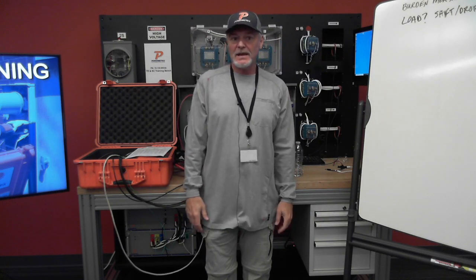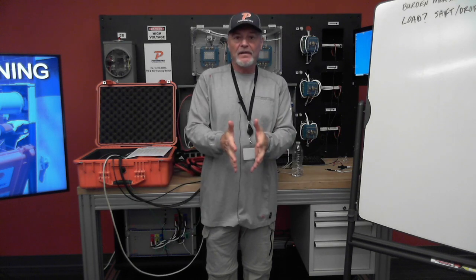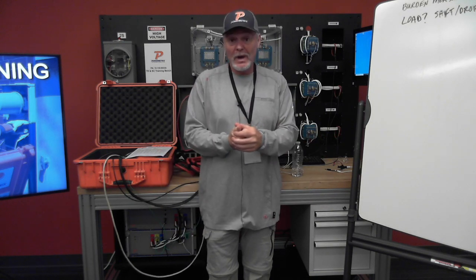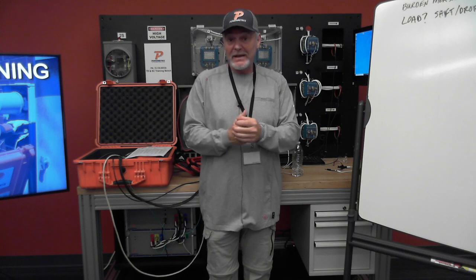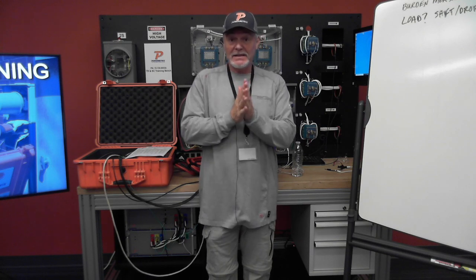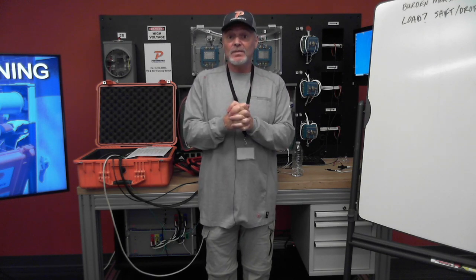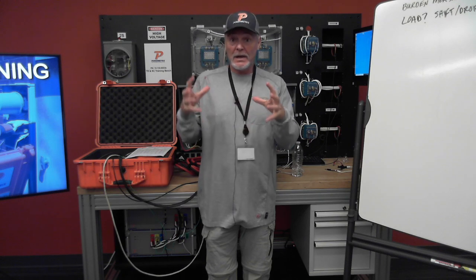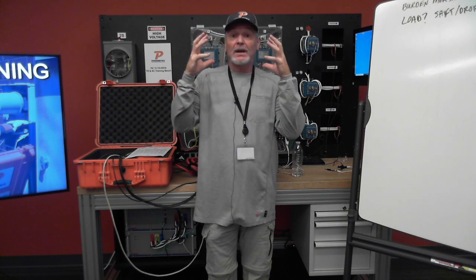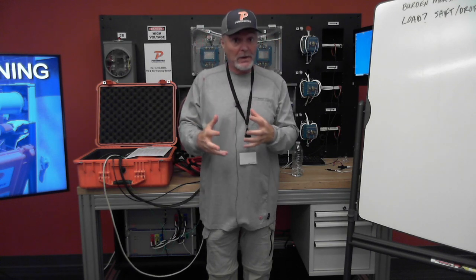In this case, it had got us down to the point where if it hadn't been corrosion, we definitely would have had to have pulled that CT and taken a look at it. So hope you got a lot out of this one. It included a lot of common sense troubleshooting, and also using the equipment really well.